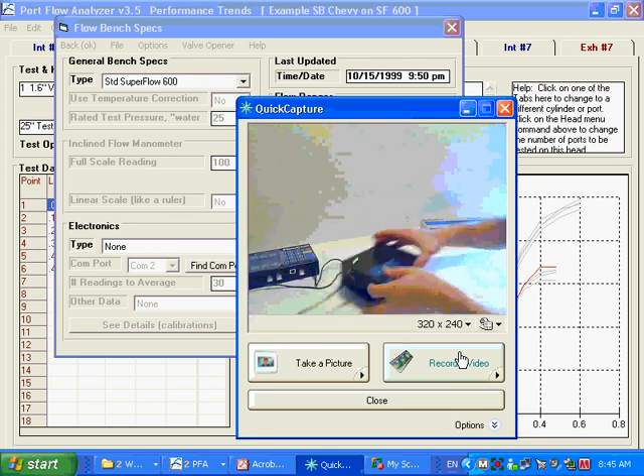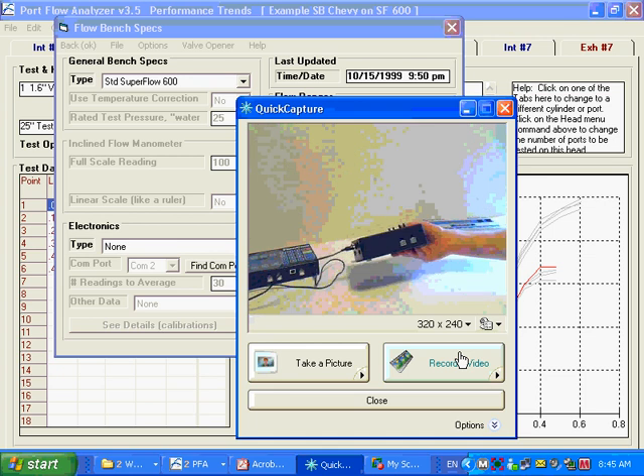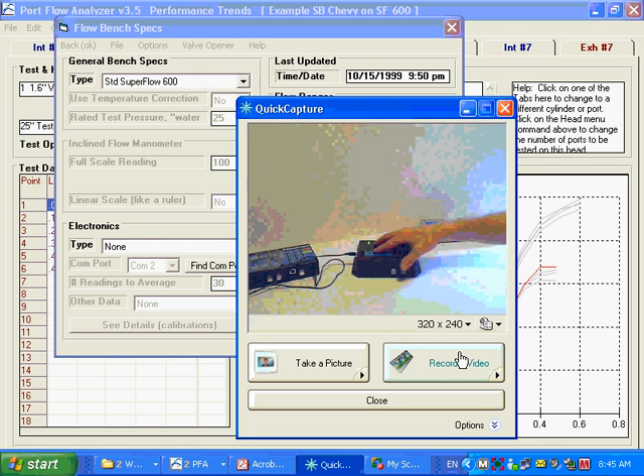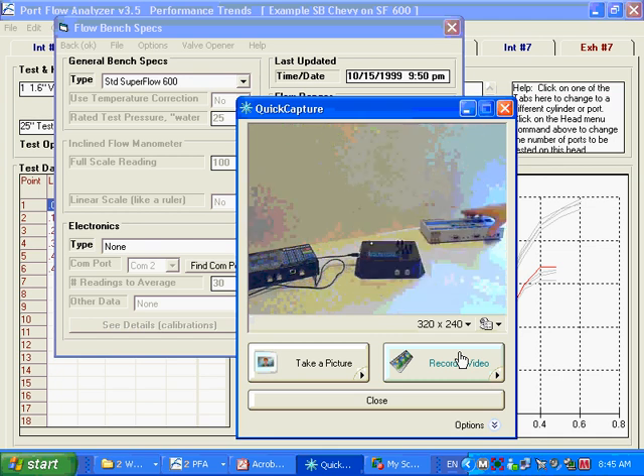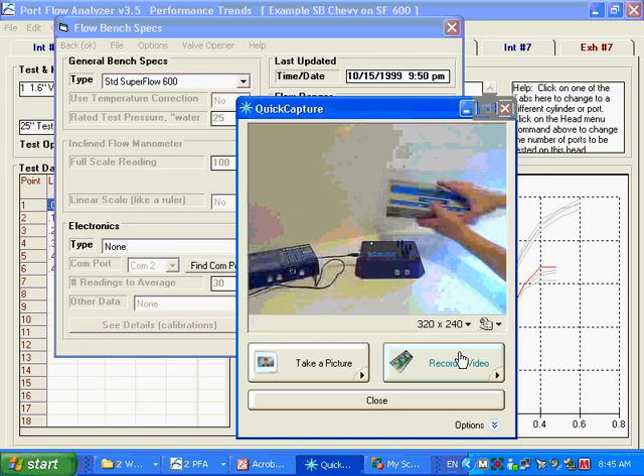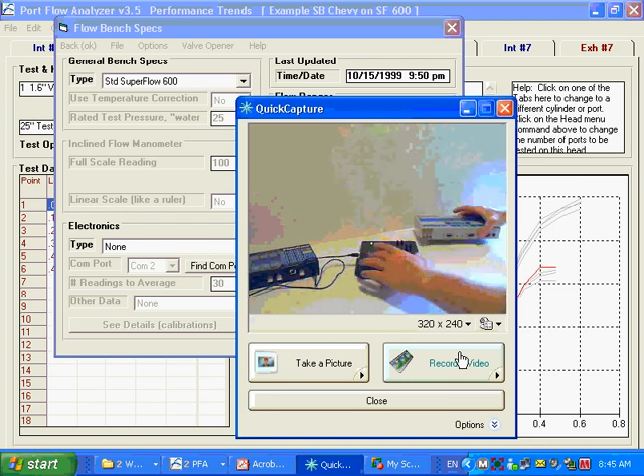And then we have our black box, which is real similar, three pressure taps, a couple temperature inputs, swirl meter input, and this is ours. The difference between ours and theirs is ours is quite a bit cheaper, but theirs does have this display. Their SuperFlow Flowcom can work without a computer, and you could get CFM measurements up here. With ours, you do need the computer connected to it to make it work.